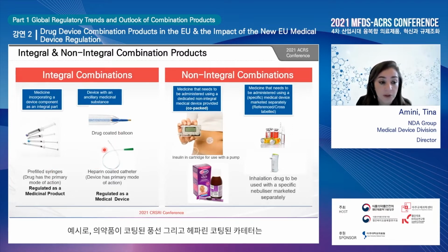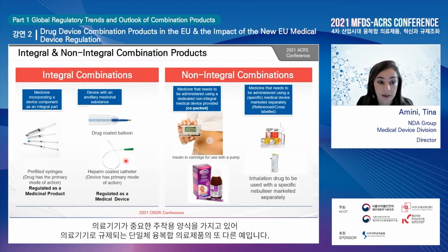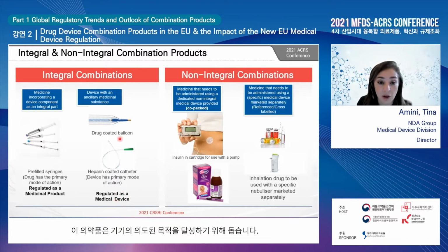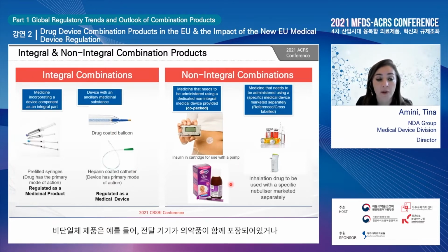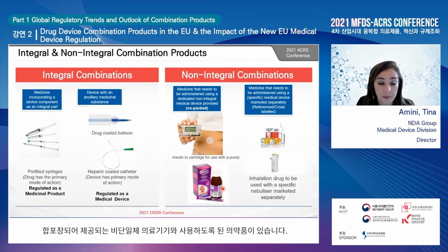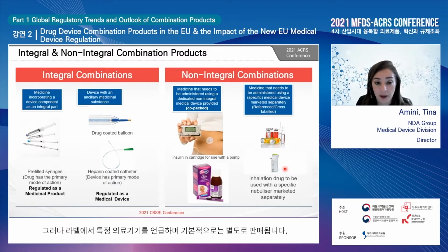Drug-coated balloons or heparin-coated catheters, for example, are other examples of integral combinations where the device has the primary mode of action, and these are regulated as a medical device. Here, the drug is assisting the device to achieve its intended purpose. Non-integral products are examples where, for instance, the delivery device has been co-packaged with the medicinal product, or the medicine needs to be administered using a dedicated non-integral medical device, which has been provided and co-packaged. And as I mentioned before, the medicinal product could be marketed separately from the medical device. However, its labeling refers to a specific medical device which is marketed separately.